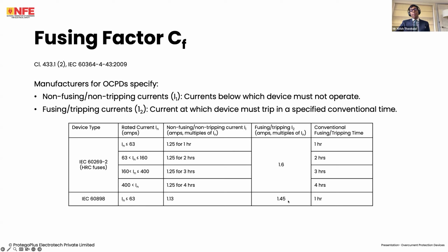1.13, sorry, my apologies, 1.45 times In, the device will trip within 1 hour. And what the conventional time and the conventional tripping current are is defined in the product standard. And this is usually for a bunch of ratings. If you look at fuses, up to 63 amps, it is 1.6 for 1 hour. Between 63 to 160, it's 2 hours. Between 160 to 400, 3 hours. Greater than 400, it comes to 4 hours. Yeah. So this is the relation here.